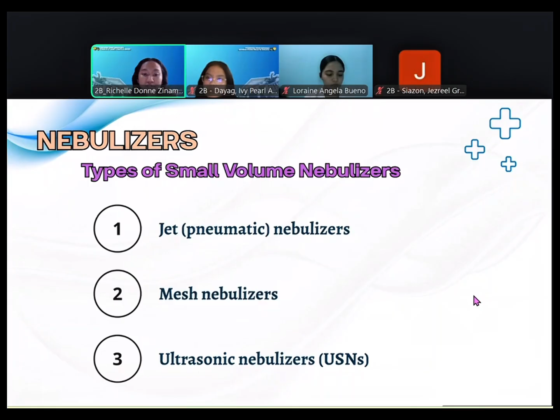Under jet pneumatic nebulizers, these are small reservoir, gas-powered aerosol devices. They are also termed as handheld nebulizers, updraft nebulizers, and unit dose nebulizers. Commonly for jet nebulizers, in the traditional type, they have a high drug wastage, mainly inside the device itself. And its operating principle is the jet shearing principle.